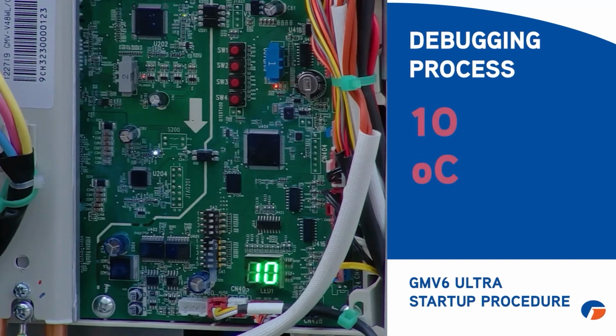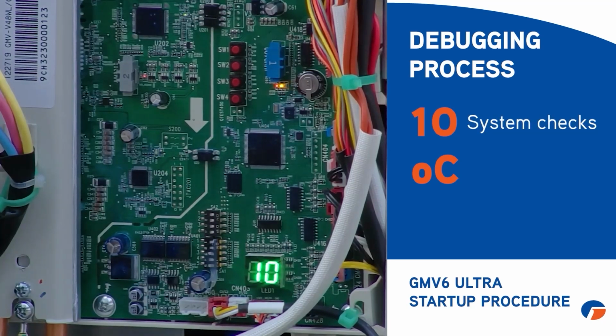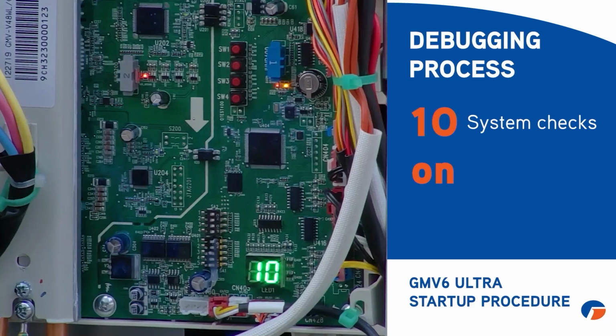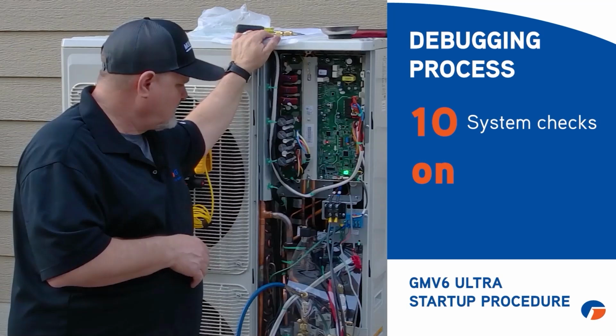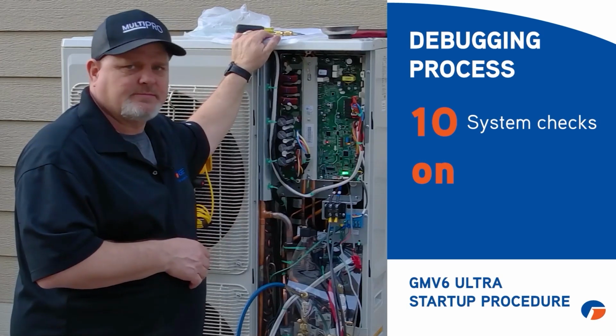So now it's in step 10. At step 10, it's going to start the compressor for a minute, start the fans for a minute, and probably cycle the indoors a little bit. It's doing its own checks. It's making sure you opened the service valves. This machine's smart enough that if you didn't open those service valves, you're going to get an error code. This whole process only lasts about 2 minutes, and then once it's done, it'll move into step 11.